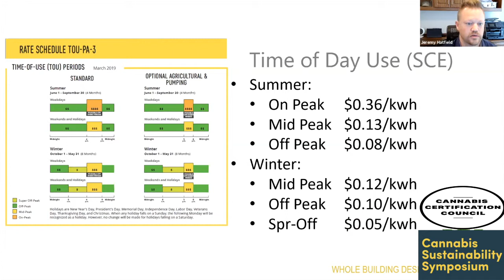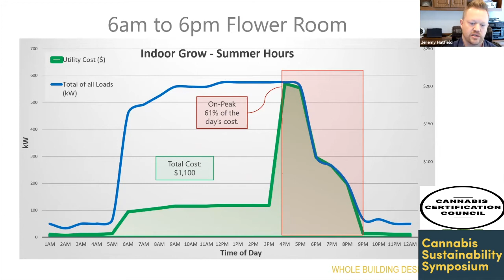We took our design and plotted our total loads. The blue line is our total load profile, and then we applied our utility costs—this is basically HVAC and lighting costs. You'll see this red area is that 4 to 9 p.m. window, and that makes up 61% of the daily cost, estimated at $1,100 a day—a huge 61% for that one 5-hour period of the day.